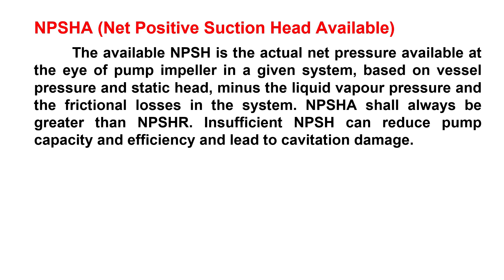NPSH-A — Net Positive Suction Head Available. The available NPSH is the actual net pressure available at the eye of the pump impeller in a given system, based on vessel pressure and static head, minus the liquid vapor pressure and the frictional losses in the system. NPSH-A should always be greater than NPSH-R; insufficient NPSH can reduce pump capacity and efficiency and lead to cavitation damage.